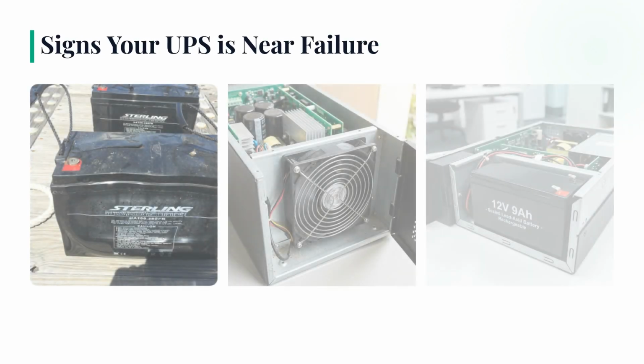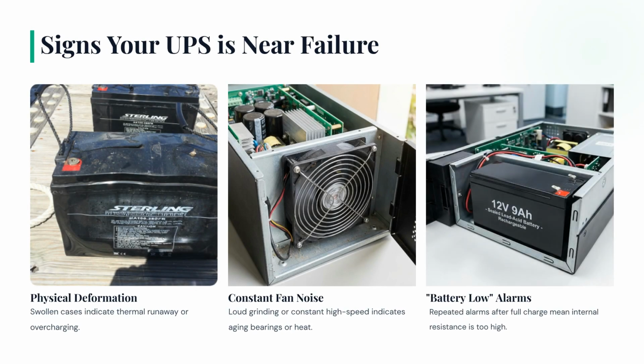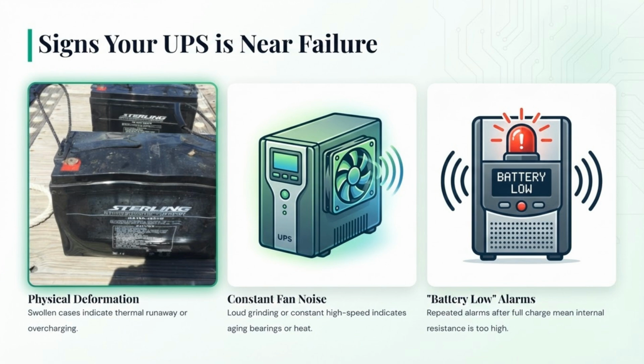Key signs of impending failure include physical battery deformation, constant loud fan noise indicating aging bearings, and repeated battery low alarms even after a full charge. Recognizing these warning signs allows for timely intervention, preventing sudden loss of critical power protection.